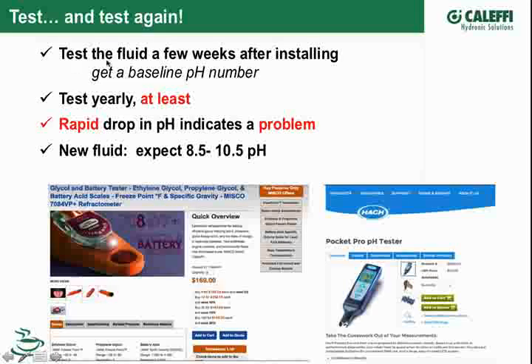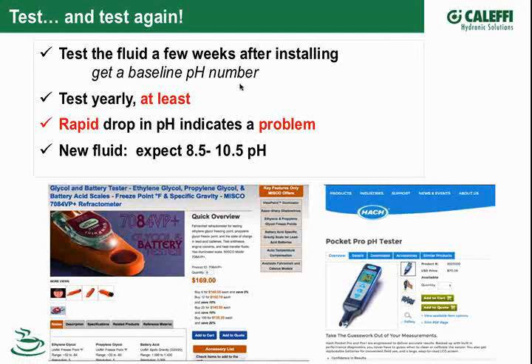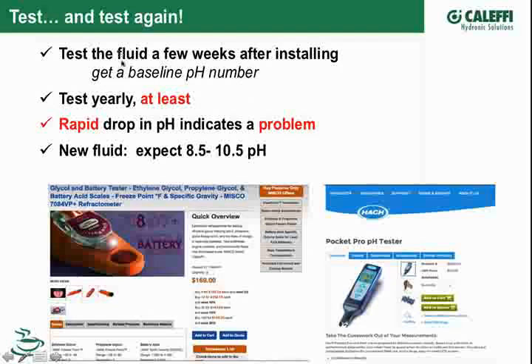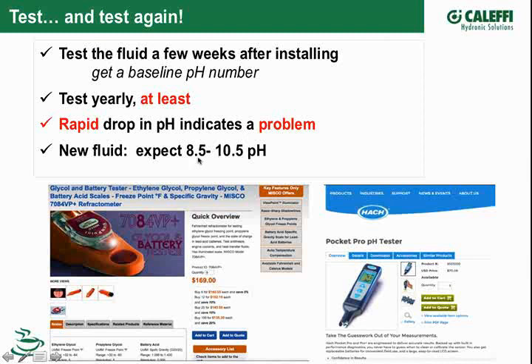I like the point about going back a week or two later and checking it then - that gives you your baseline. Then every year, or every couple years on a service call, check it again, because if it's moving, that's the real indicator, more than where it is, but the fact that it keeps moving down. Get that baseline, make sure you did everything right. If you do it right the first time, you'll reap the rewards with a long-performing, adequately performing system. If you do it wrong, you're going to pay a price - it's just a matter of when.